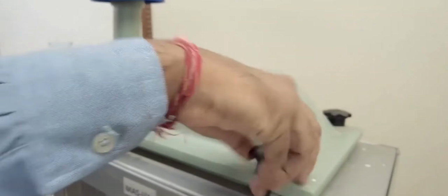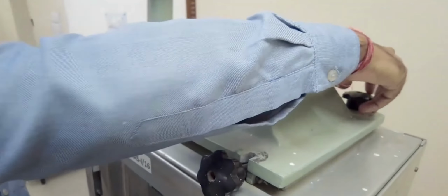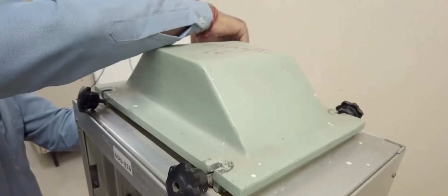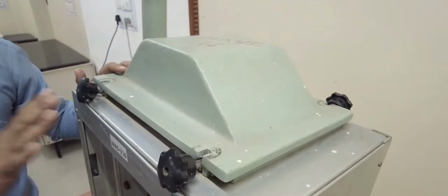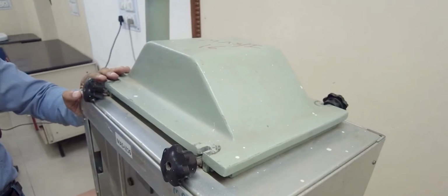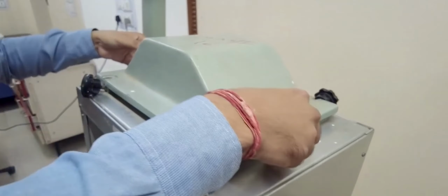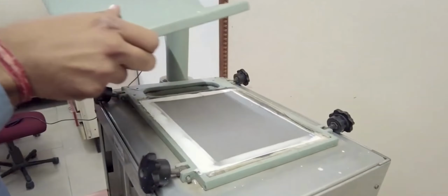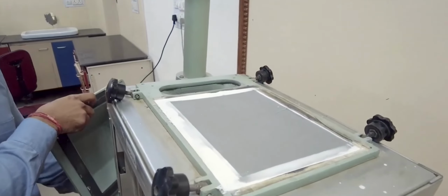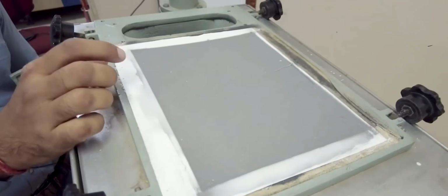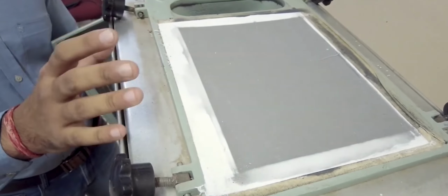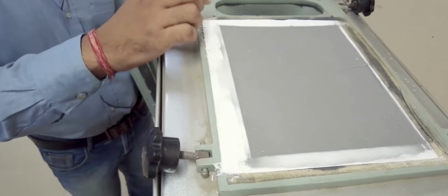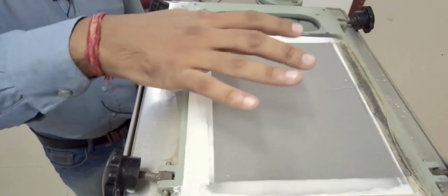Before starting the instrument, we have to place the filter into the filter assembly. So I'll tell the different components of it. This is the filter cover. We have to take it out very gently, and you can see that a filter is already present, pretty dark, indicating that some sampling has already been done. This is the 8 by 10 inch filter, and this is the upper cover.